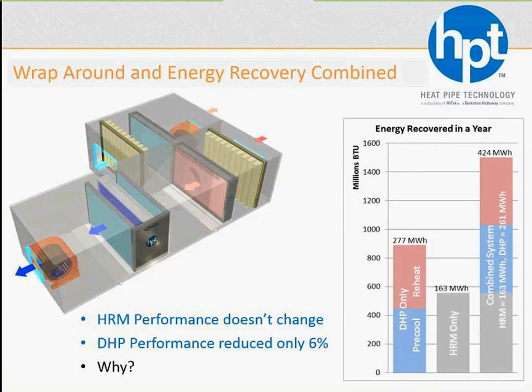Take a look at this particular example. If we do DHP only, as in wraparound heat pipes, we are saving 277 megawatt hours. Pretty extensive. HRM only, again, this particular facility, this particular example, 163 megawatt hours. Combining them, you're looking at 424 megawatt hours. So pretty substantial savings. Now, in some locales where it's mainly summer recovery, the DHP or wraparound heat pipe may take a little bit more of the hit. But again, you need to do the numbers for your particular facility to see which works best for you, the combination of the two, or one or the other.